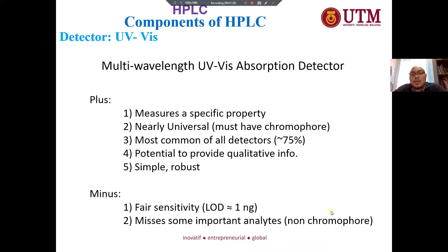However, the UV-Vis also has disadvantages. Fair sensitivity, it is not that sensitive. It is sensitive at the ppm level, I can say, but not until the ppb or ppt level, and it can miss some important analytes, especially the ones without a chromophore. That is the weakness, the disadvantage of the UV-Vis.